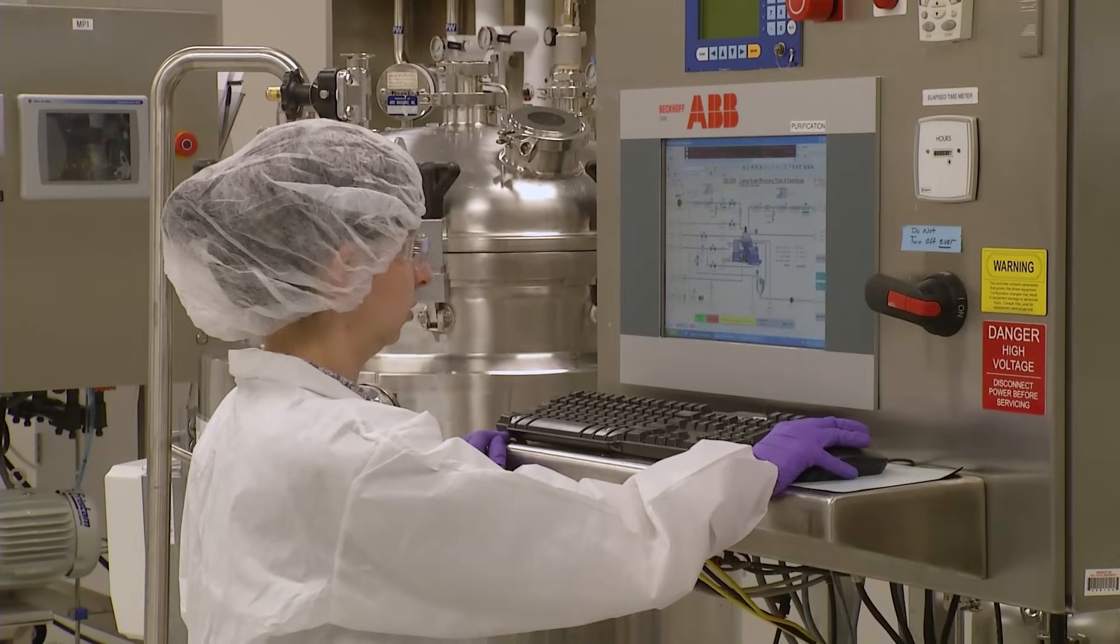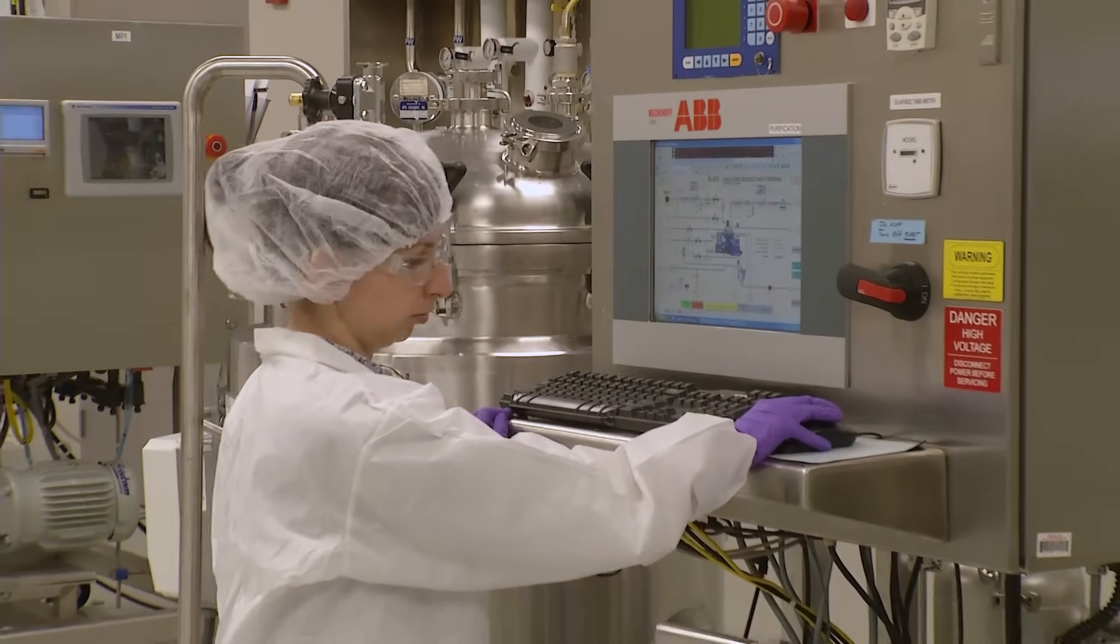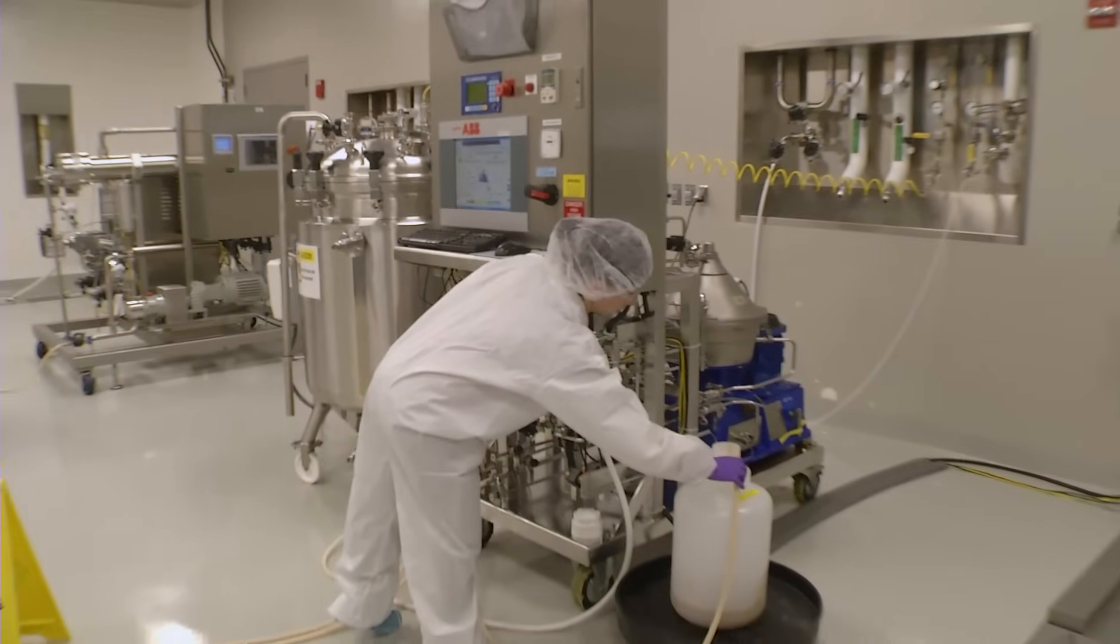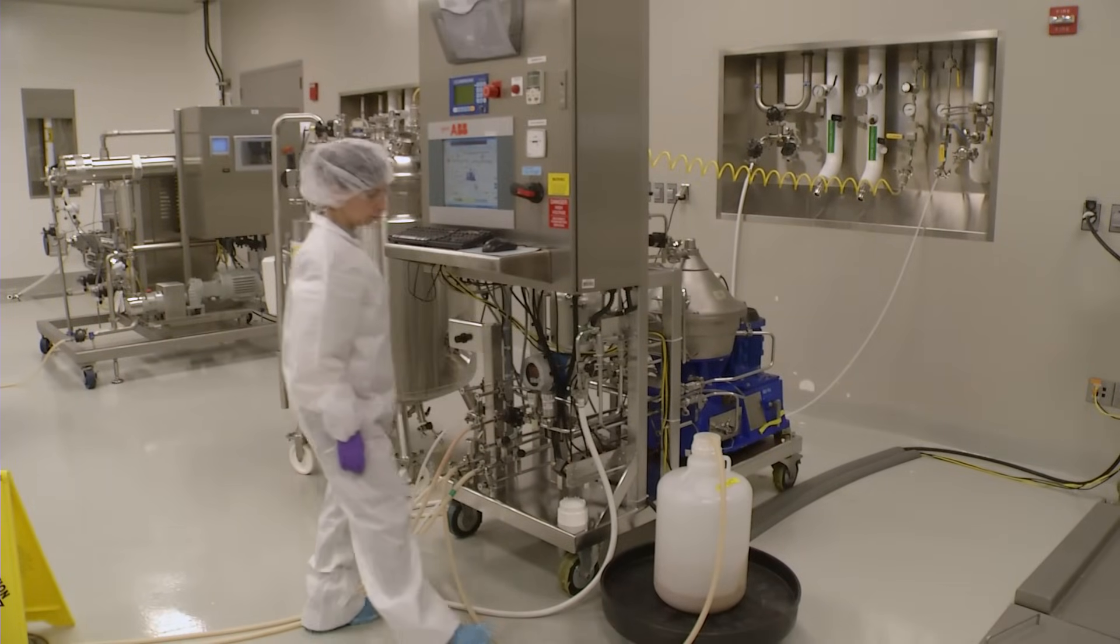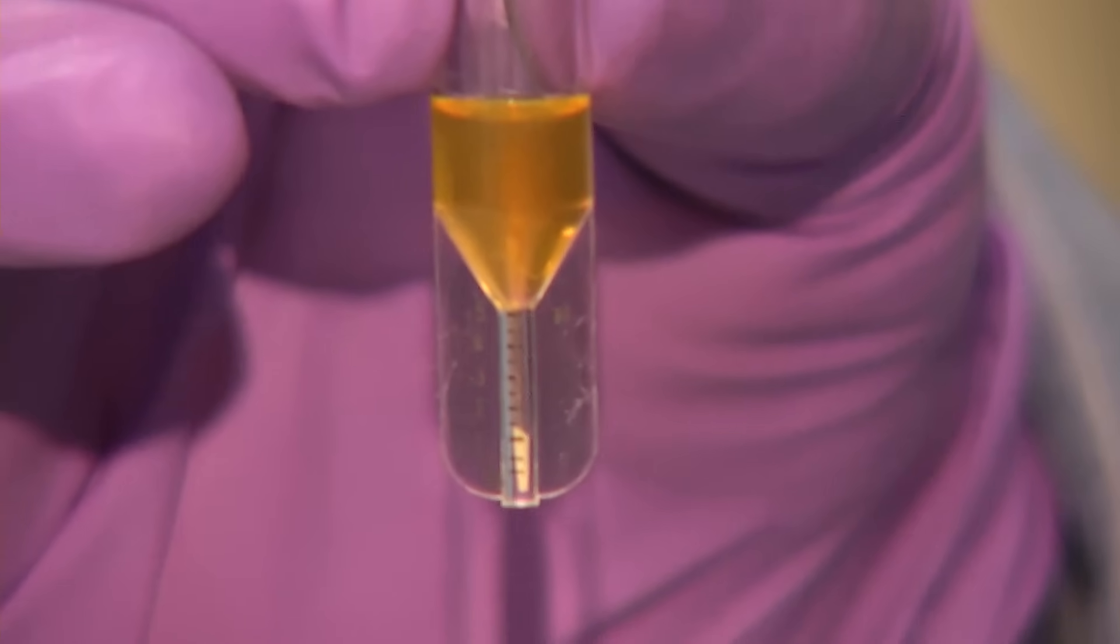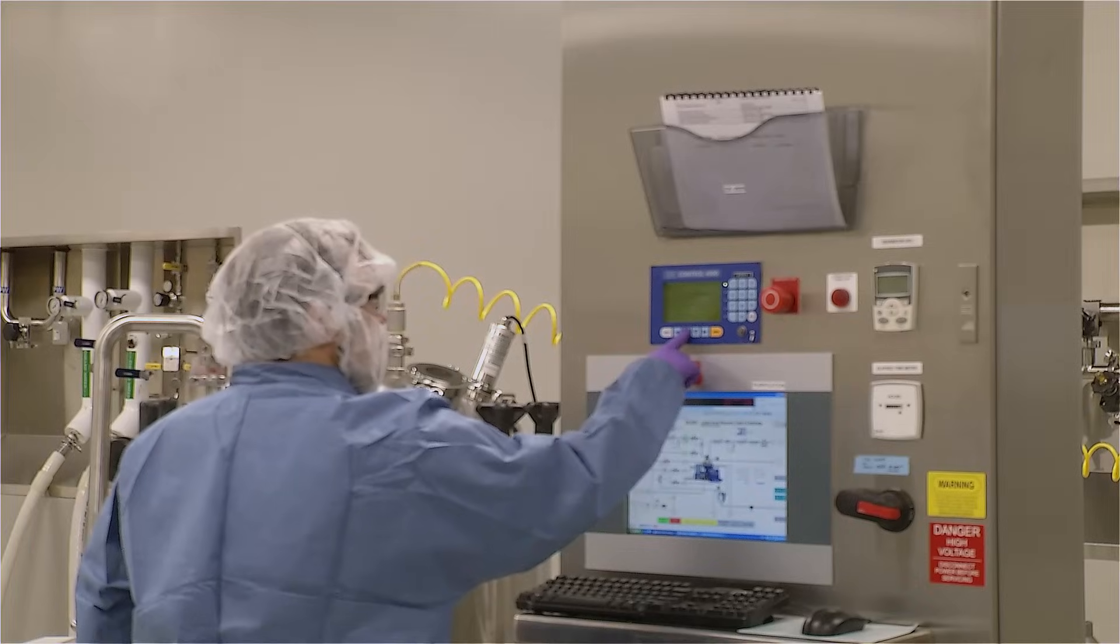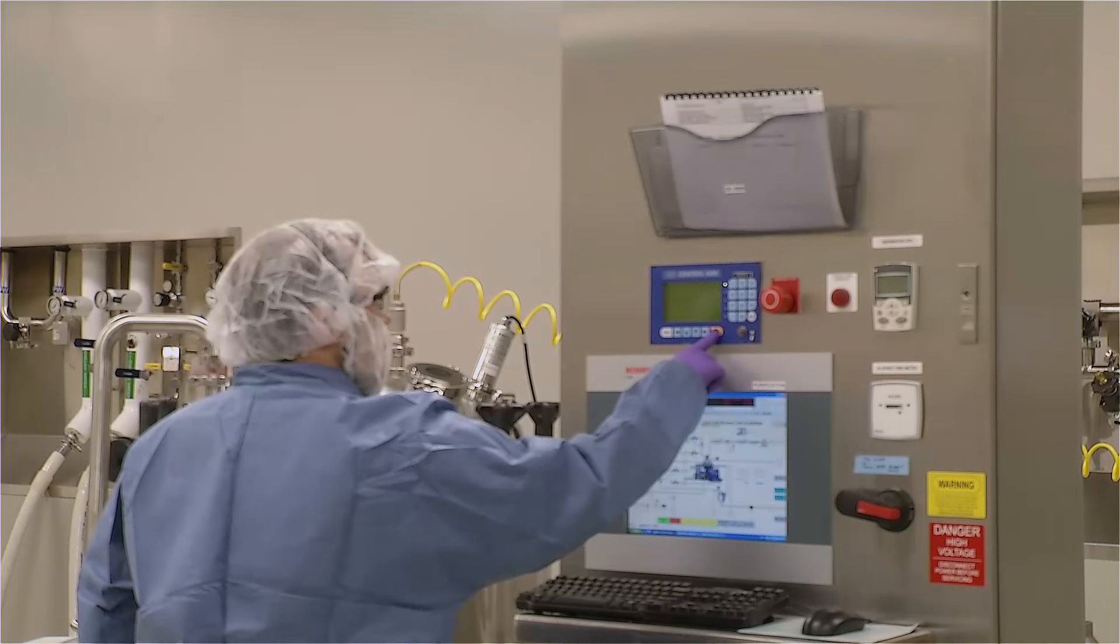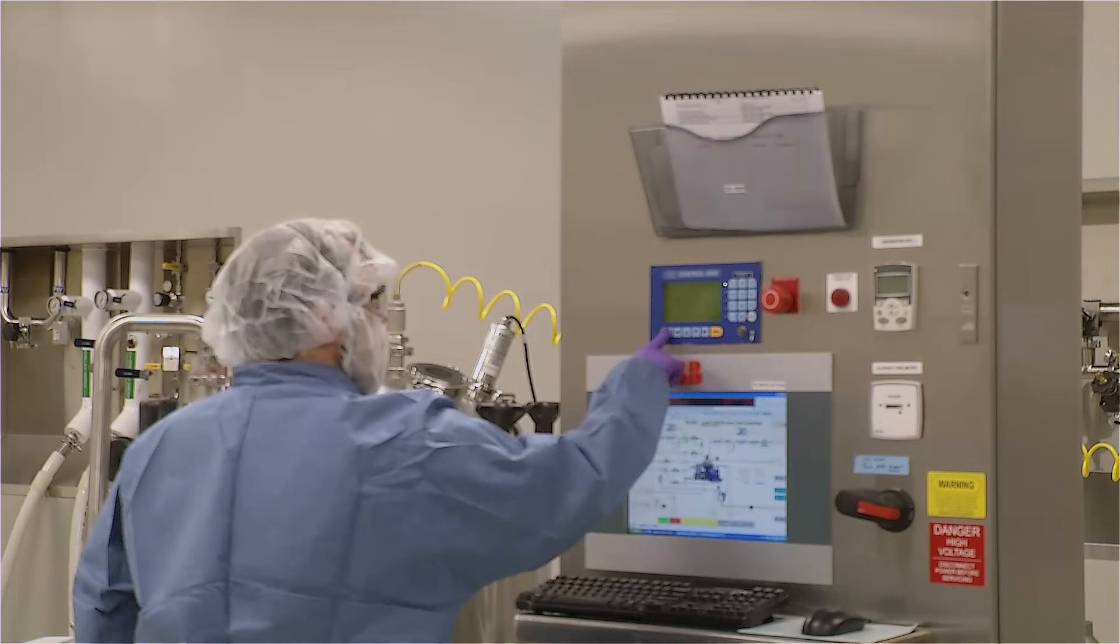The centrifuge has an integrated RPM monitor. If the unit is not rotating at a stable running speed, the controller will alarm and shut it down. The liquid leaving the bowl is known as the clarified stream because almost all the solids have been removed. A sensor monitors the clarified stream for percent solids. When this value rises, it indicates that the bowl is at capacity and the solids must be removed before processing more broth.